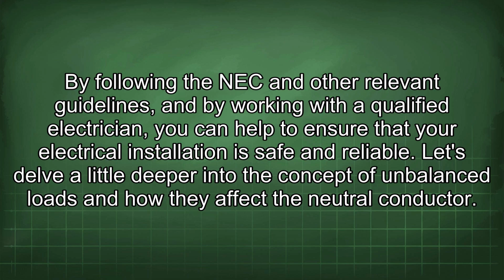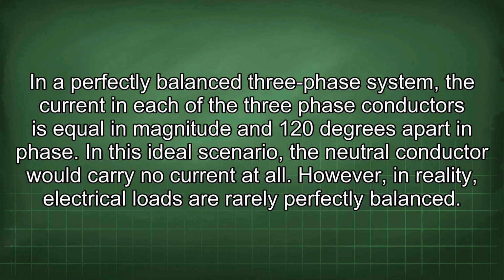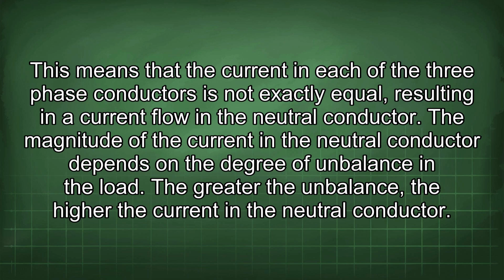Let's delve a little deeper into the concept of unbalanced loads and how they affect the neutral conductor. In a perfectly balanced three-phase system, the current in each of the three-phase conductors is equal in magnitude and 120 degrees apart in phase. In this ideal scenario, the neutral conductor would carry no current at all. However, in reality, electrical loads are rarely perfectly balanced. This means that the current in each of the three-phase conductors is not exactly equal, resulting in a current flow in the neutral conductor. The magnitude of the current in the neutral conductor depends on the degree of unbalance in the load. The greater the unbalance, the higher the current in the neutral conductor.